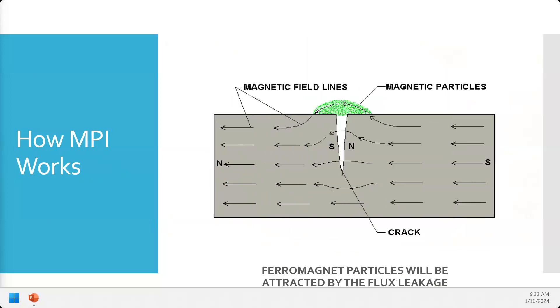This is what the particle indication looks like once we've placed our particles on the surface. Modern magnetic particle inspection uses particles coated with a color or fluorescent coating — essentially iron dust — which helps us see the indication even better.